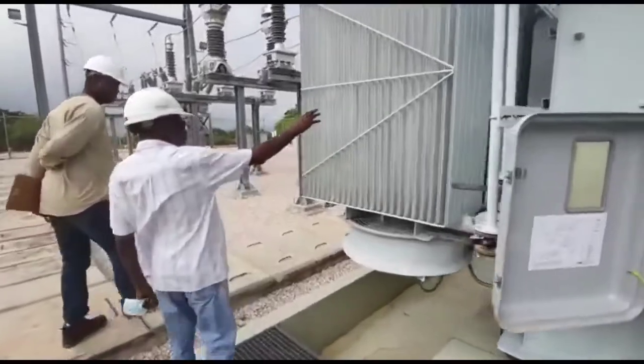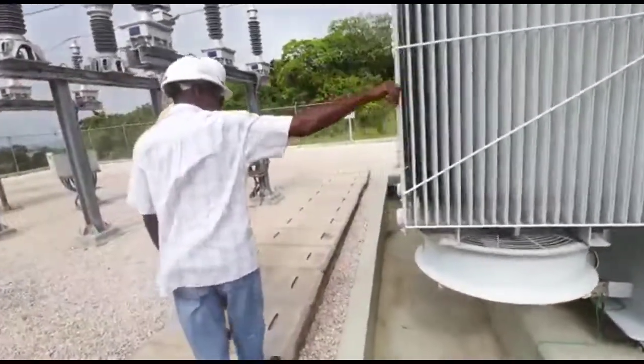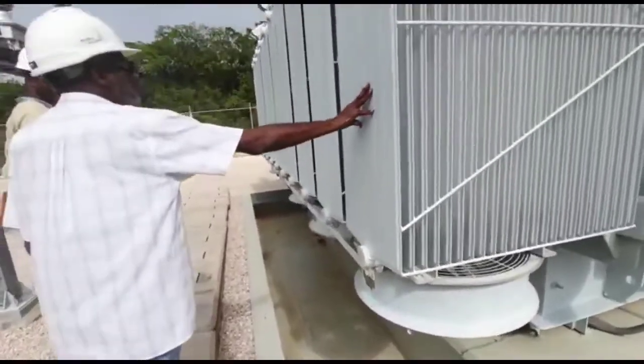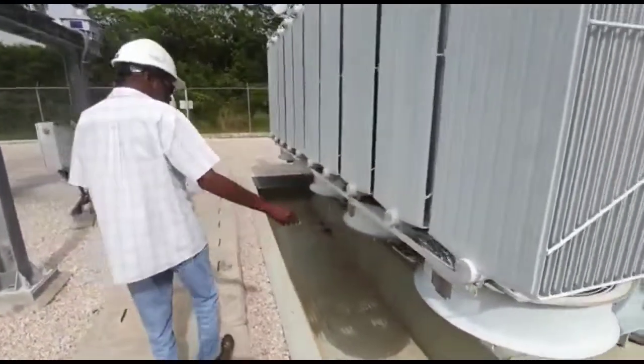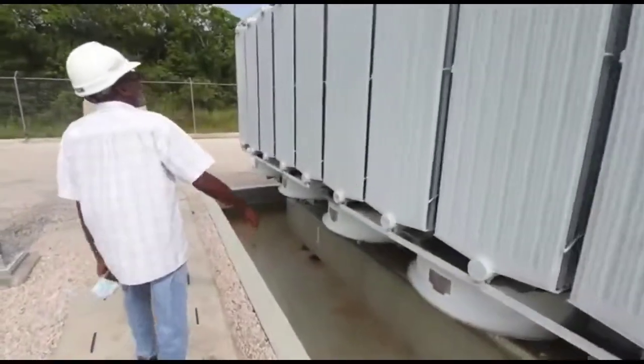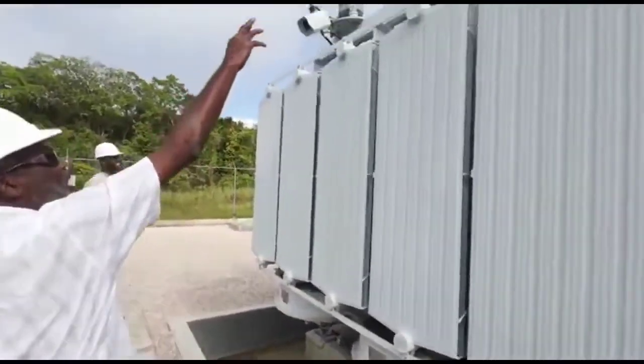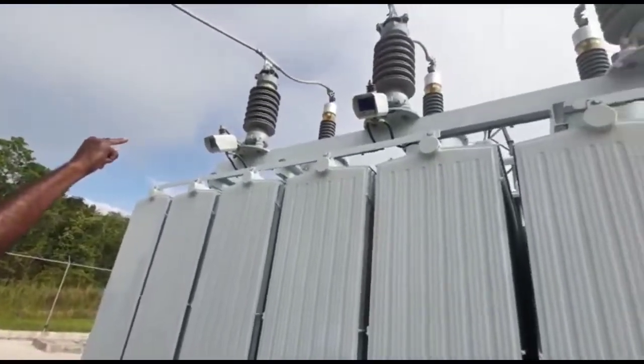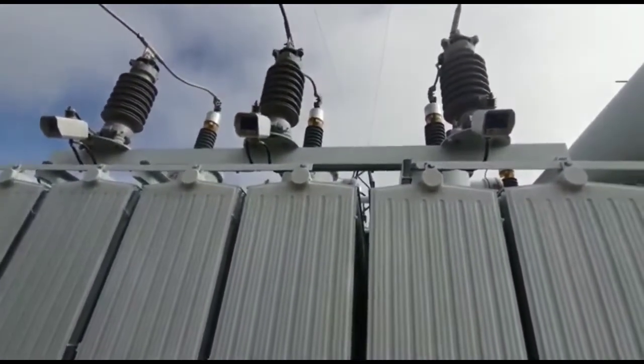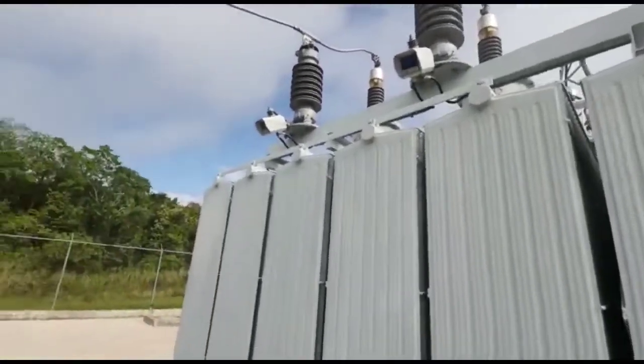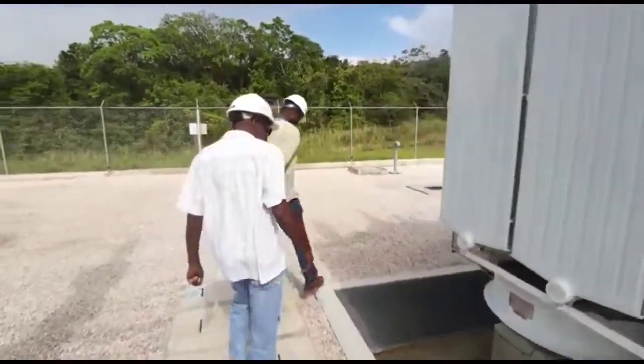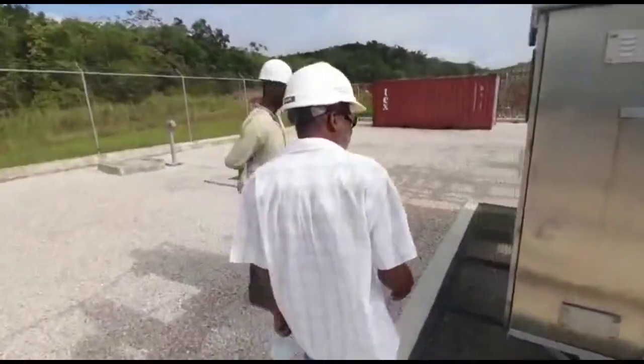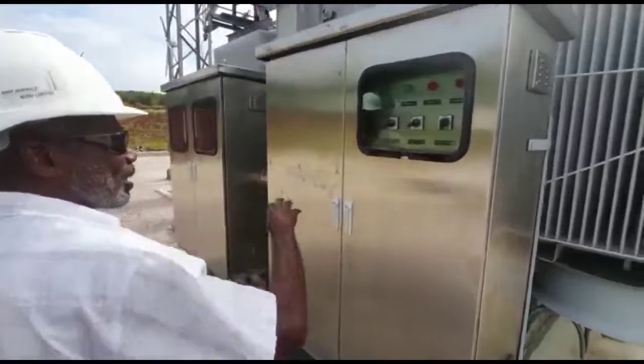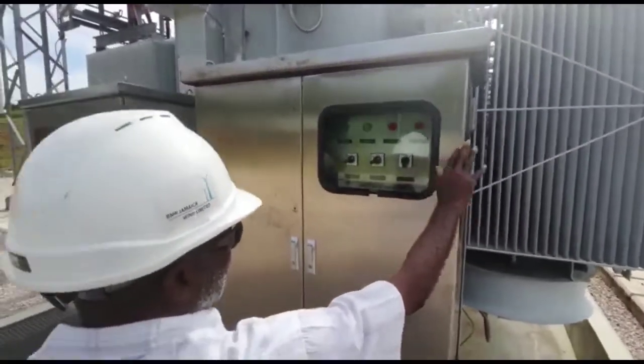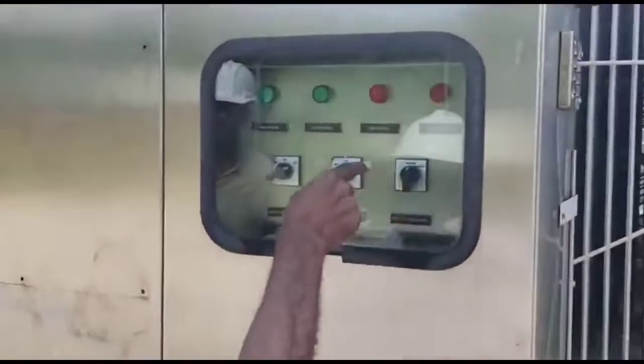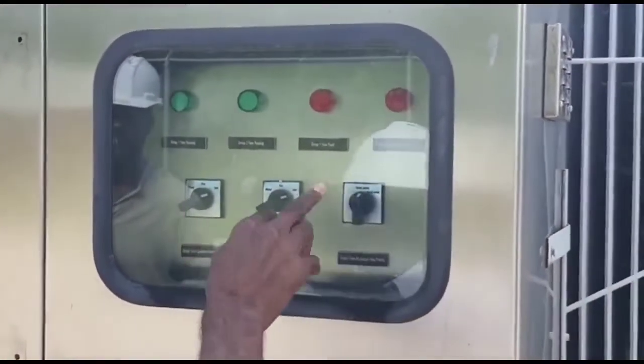On this side of the transformer we have some radiators and fans, and the radiators are used to cool the oil, and the fans are used to cool the radiators. We go around here and we see that we have some bushings and CTs and VTs, voltage transformers and current transformers that give us the measurement on the transformer. Then around here we have the control panel for the fans, and you can select which set of fans you want to run, and based on your selection you adjust these accordingly.